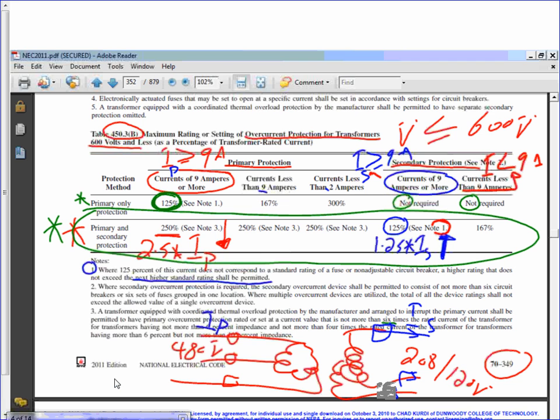Then, if you look at the primary side, guys, they tell you primary only protection, and primary and secondary protection. Typically, your default is primary and secondary protection. If your amps are less than 9 amps, those are smaller transformers. Our primary current is more than 9 amps. So what's the multiplier to size the overcurrent protection device? Can you see it? 250. So my multiplier is 250. Any comments, guys? Any questions?